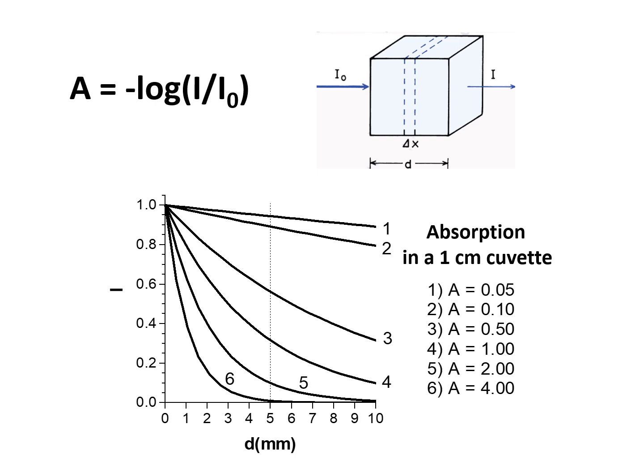Then we found that we had to dilute the sample even more in the fluorometer. The reason for that is not because of the inner filter effect, which is already pretty well taken care of at 0.1 absorbance, but rather because so much light is leaving the sample and hitting the detector that the detector is saturated. And when the detector is saturated, it doesn't necessarily send you a warning. It just gives you a spectrum that's not really the right spectrum.